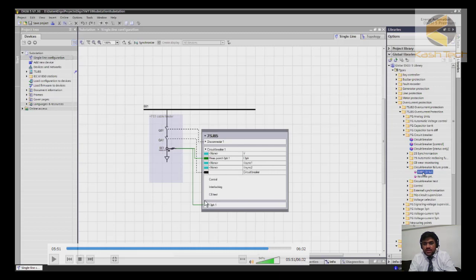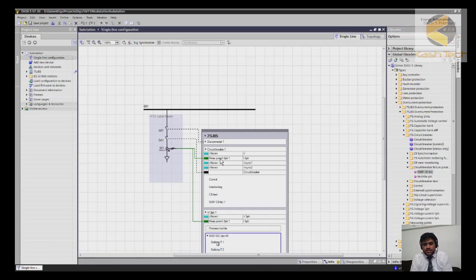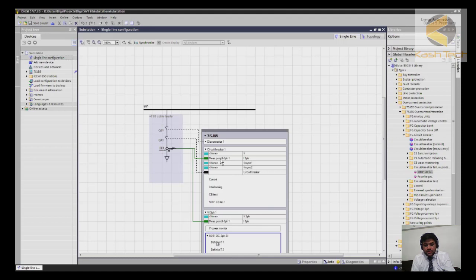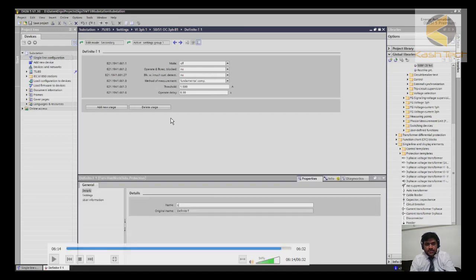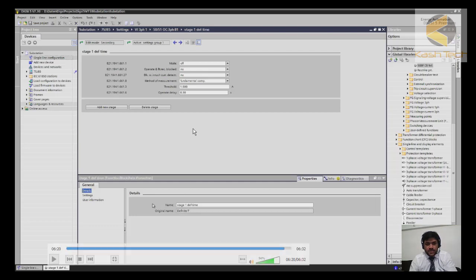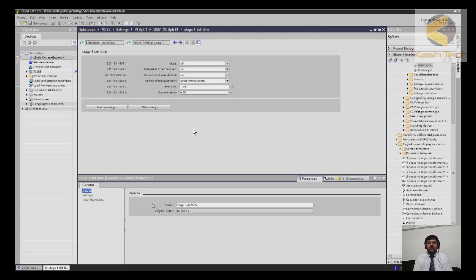Some functions are available by default in the SIPROTEC 5 device, and additional functions can be added from the global library. To view the settings, click on a specific function and you will see at the bottom the 50/51 overcurrent three-phase settings. Click on Definite Time T1 to see further settings. The function group is currently off, but other settings are available. You can go to Properties and change the name of the function.